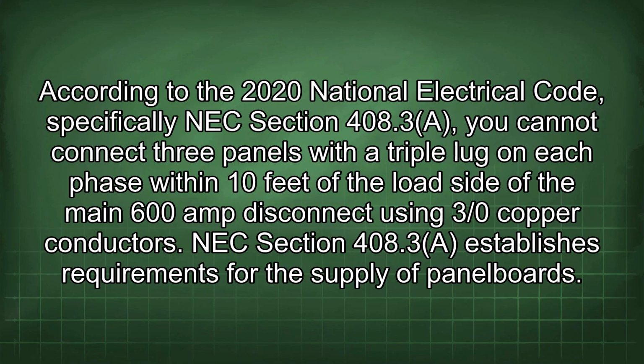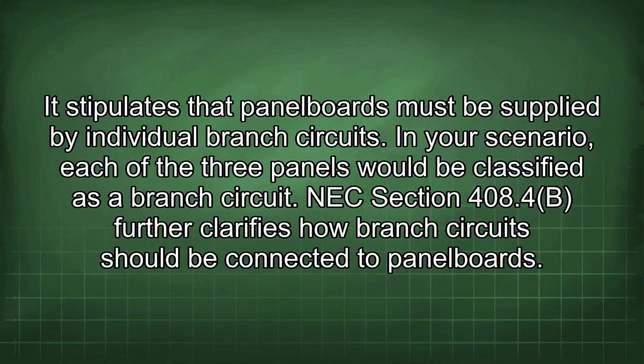According to the 2020 National Electrical Code, specifically NEC Section 408.3(A), you cannot connect 3 panels with a triple lug on each phase within 10 feet of the load side of the main 600 amp disconnect using 3/0 copper conductors. NEC Section 408.3 establishes requirements for the supply of panel boards. It stipulates that panel boards must be supplied by individual branch circuits. In your scenario, each of the 3 panels would be classified as a branch circuit.